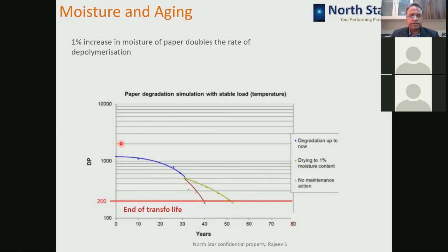This graph is depicting the deterioration in the degree of polymerization of paper insulation. A new insulation will have a DP of around 1200, and aged insulation will have a DP of around 200. So between 1200 and 200, the aging of the insulation happens.